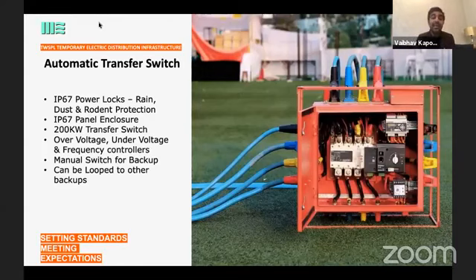Third, we can loop these changeovers. You don't need a separate backup for light, sound, or LED individually, I can loop these changeovers. Normally on site we only have sound and LED backup, not light backup, for reasons known and unknown. So as a power distribution company, with the same backup given for sound and LED, we create a backup for light as well, because your light is also important to us. We don't want a light genset to fail and have the blame come on the power distribution company. So that's simply how these automatic changeovers work on these systems.